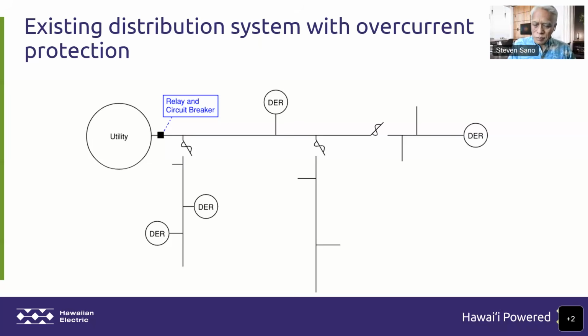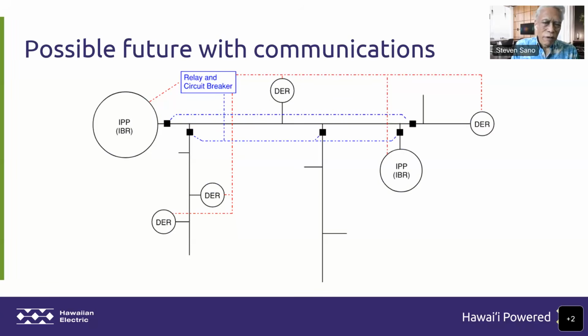As our distribution circuits change with more and more inverter-based generation, we think we'll have to change out things like fuses. So in this diagram, you see the fuses replaced with circuit breakers or reclosers, other devices, and communication everywhere. We need communication to the protective devices, and also to and from the generation sources that we'll possibly have on our circuits here. So again, distribution, although for the most part radial, does need significant changes.